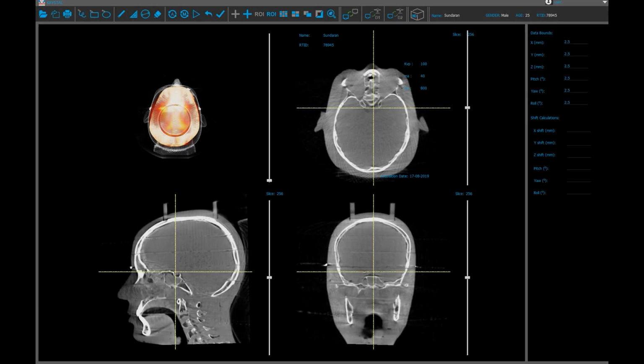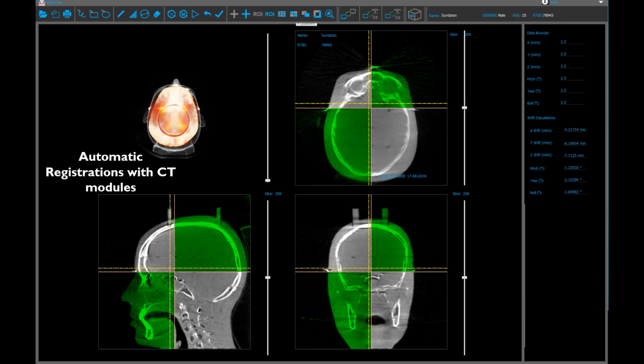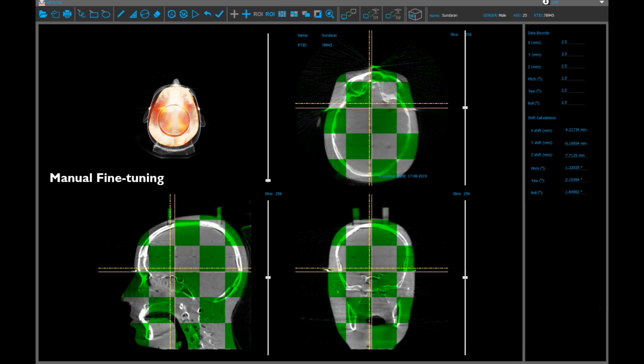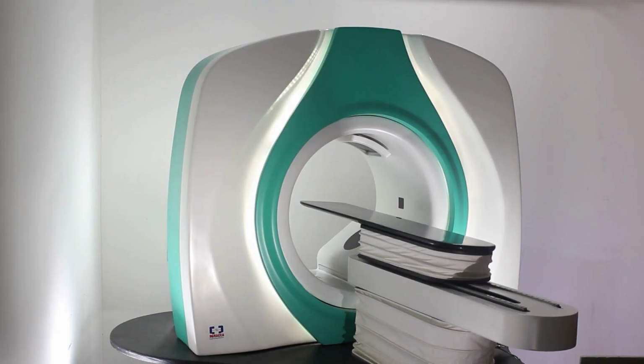To see what we treat is highly imperative in radiation oncology, Siddharth II is equipped with in-gantry imaging through a pair of KV imaging modules. These modules help in generating high-resolution CBCT along with stereotactic imaging at all gantry angles. These images are used to find patient setup errors using registration algorithms. The setup corrections are swiftly carried out by 6D robotic couch to ensure accurate positioning.